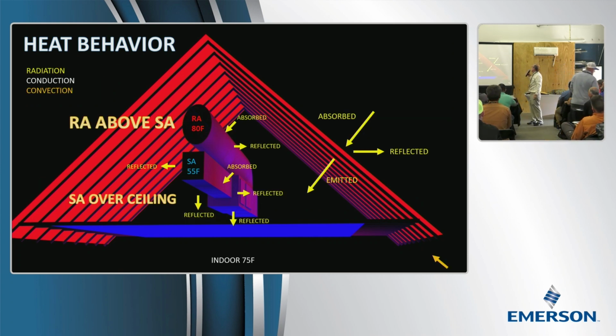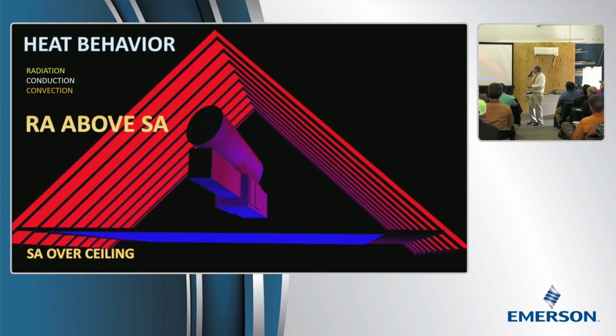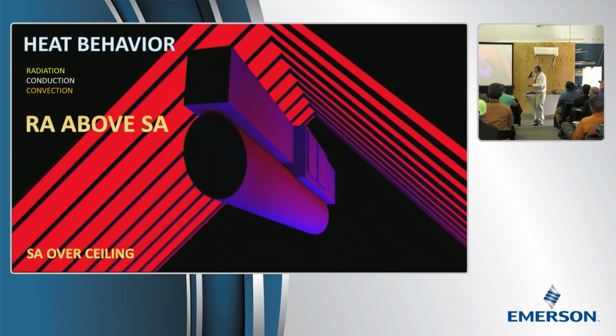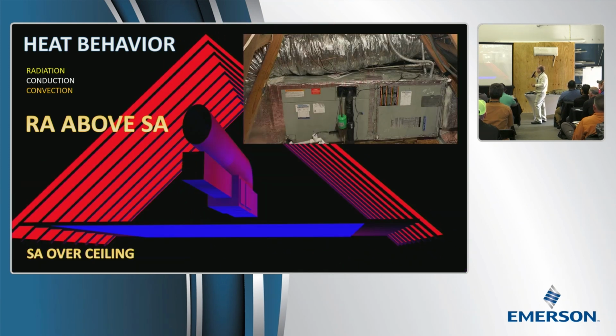All right, so we're going to look at what happens when you lay a duct on top of an air handler cabinet. This is a very common reason that ducts would sweat. If you lay a duct on top of an air handler cabinet, you're shading it. There's no radiant heat. The worst thing you can do is let it actually touch, but it would be better if you just didn't have any duct on top of it at all.